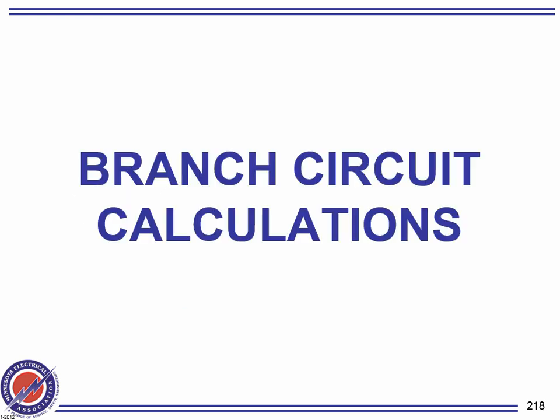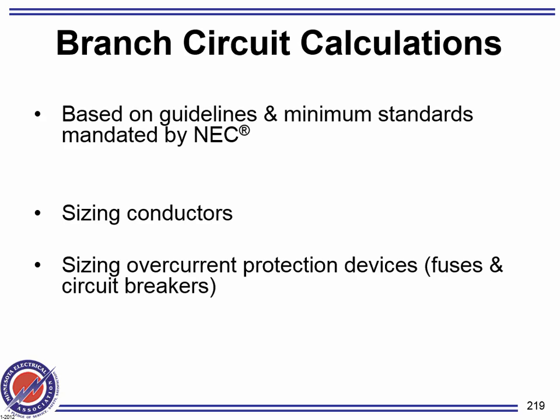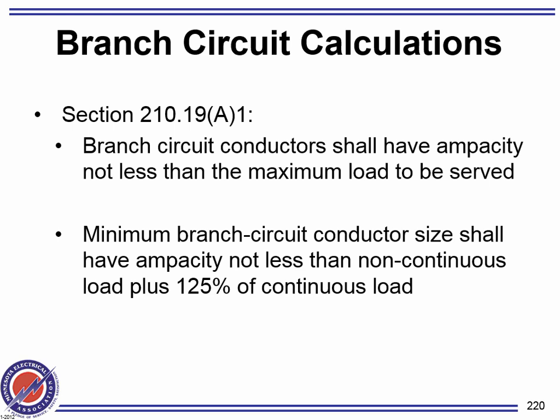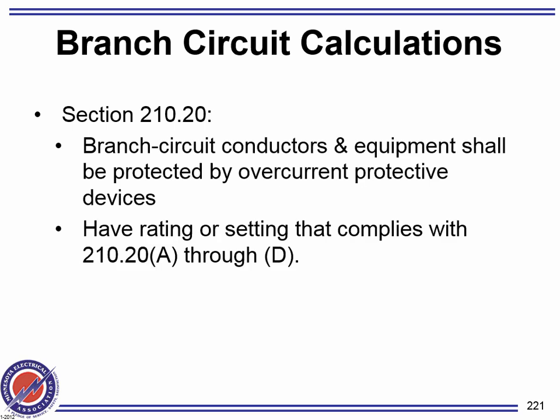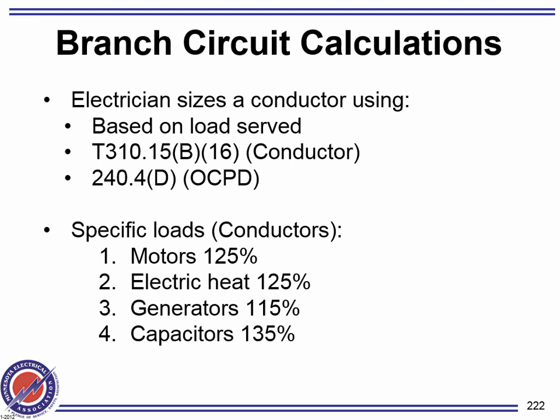Okay. Let's go ahead and talk about branch circuit calculation, gentlemen. Branch circuit calculation. Sizing conductors. A branch circuit shall have an ampacity not less than the maximum load. If it's continuous, it has to be 125 percent, like we said. It should be protected by an overcurrent protection device.